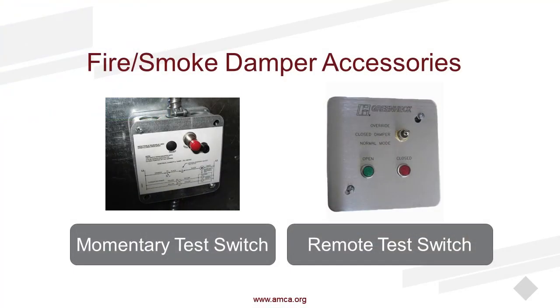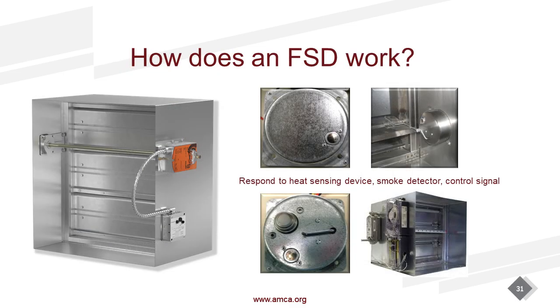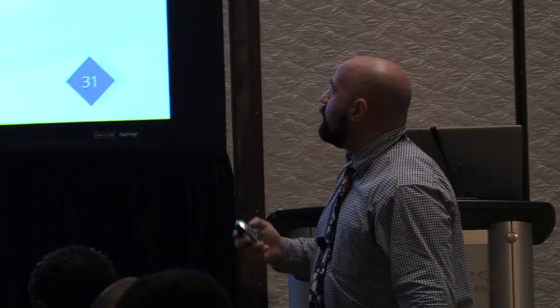The last device up there is a combination of a heat sensing device and what we call a position indicating device. So for the maintenance and testing of dampers, we can give them the capability to report their position, fully open or fully closed, back to another signaling device, maybe a fan, a fire alarm control panel, building management system, something like that. We can interlock it with another piece of equipment, and that blade device tells us the true position of the damper.